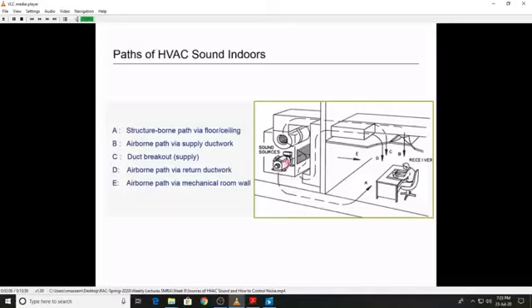Well, the vibration from the unit can go through all of the structures that it has access to and then re-radiate into the room as structure-borne noise. The most obvious path is noise coming through the ductwork and passing right out through the supply grills. But it can also come out of the return. The sound doesn't care whether it's going out the supply or the return. It will go both ways just as happily.